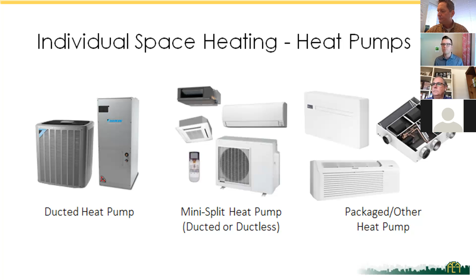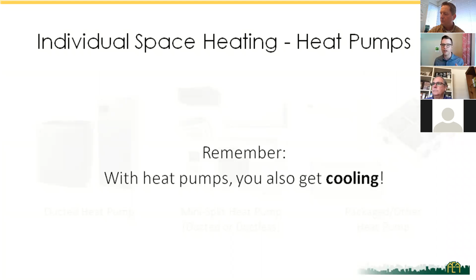Mini splits can be ducted or ductless, and we'll look at other options in a minute. The ducted heat pump on the left is more of a traditional form factor, like a large AC outdoor unit—you'll see these in smaller buildings with plenty of space outside. The fan coil or air handling unit looks very similar to a furnace, just with refrigerant running between the two units. Remember, this is for heating with a heat pump, but you also get cooling—you get both in a single system. You don't need to spec a furnace and an air conditioner separately; you just do a heat pump and you get both and you're done.